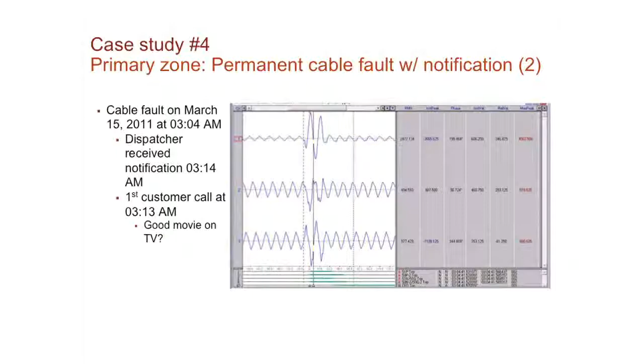But there's another real-time detection by our Ref 615 serving the information up to the COM600 station computer, and then it's performing the analysis and not only just saying the cable fault with the date and time, the substation, and the feeder name, but also saying that it was interrupted by fuse and the size fuse. We did get some switching operations or transients, so that's just valuable to know.